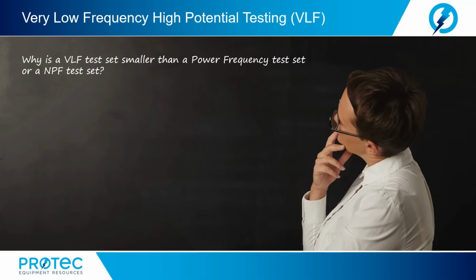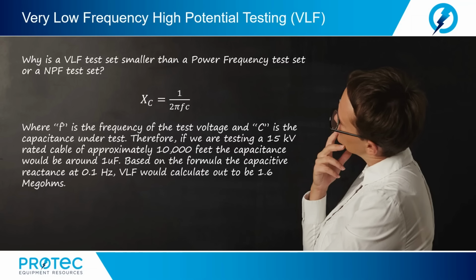Now, why are VLF test sets smaller than the power frequency test sets and even smaller than the near power frequency test sets? Well, again, let's just go back to capacitive reactance, 1 divided by 2 pi FC. Once again, F is the frequency of the test voltage, C is the capacitance of the device under test.